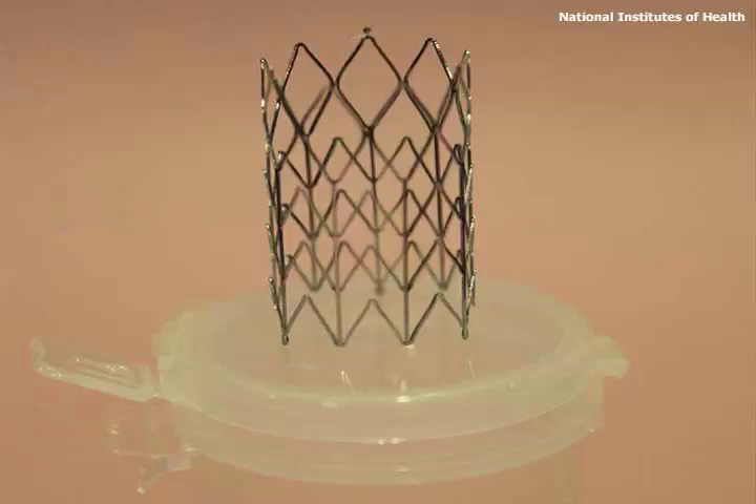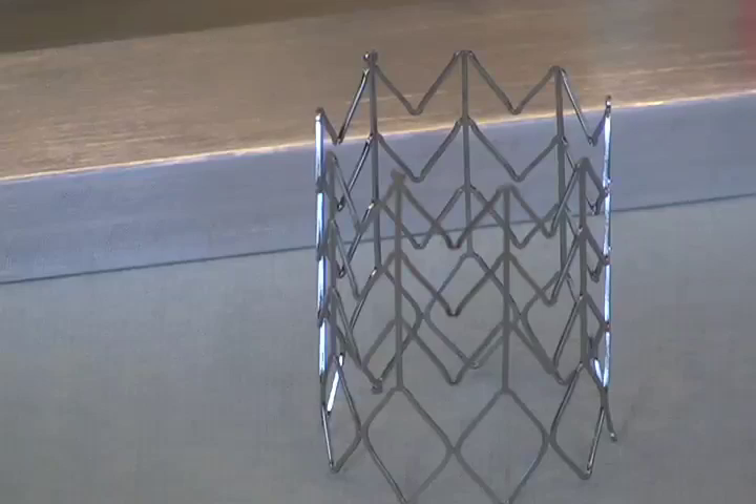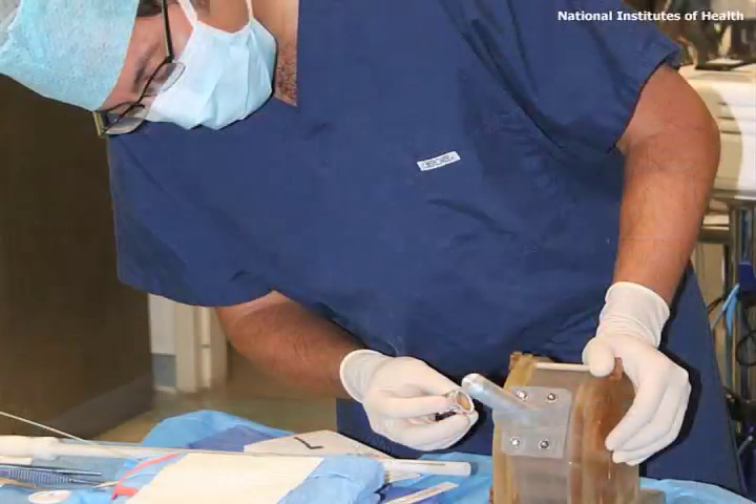The current day research might best be represented by that of Dr. Keith Horvath. His research is in the use of a self-expanding stent to which he sews a porcine, or pig, valve. The flexible stent is a design that springs open to be a structural support but collapses to allow it to be threaded through a catheter. In order to get from the large diameter of the expanded stent with the valve attached to the small diameter required to go through the catheter, this unique little apparatus was designed to collapse the diameter. You press down on the arm to slowly decrease the opening within this container, so you thread the stent and valve inside and then compress it in order to reduce its diameter for use.